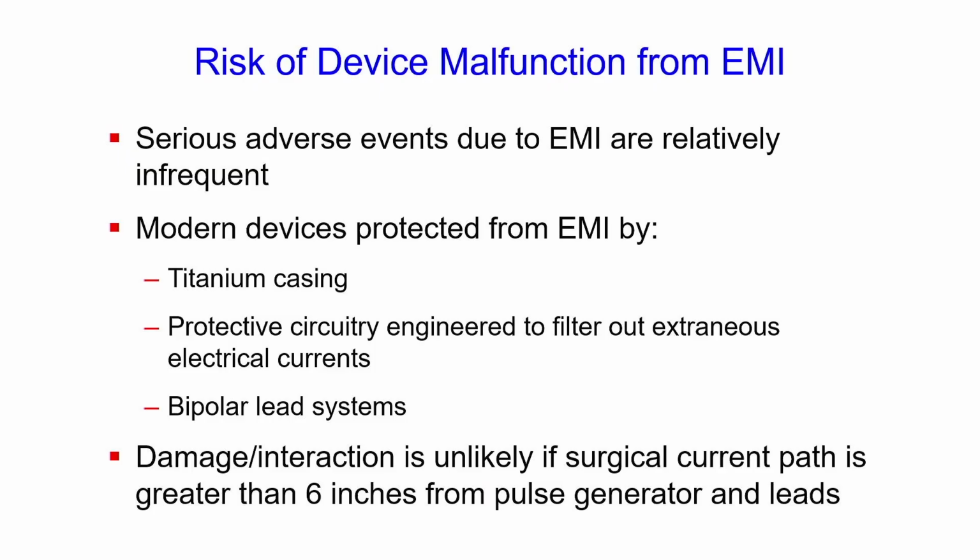What is the risk of EMI causing problems? Well, serious adverse events due to EMI are relatively infrequent. Modern devices are protected from EMI to some degree by the titanium casing, by circuitry that filters out extraneous electrical currents, and by bipolar lead systems. So damage is unlikely if the surgical current path is more than 6 inches away from the pulse generator and leads.